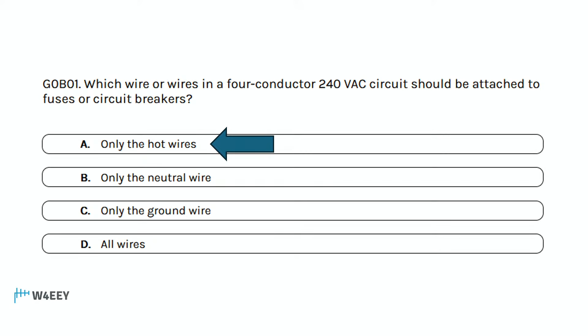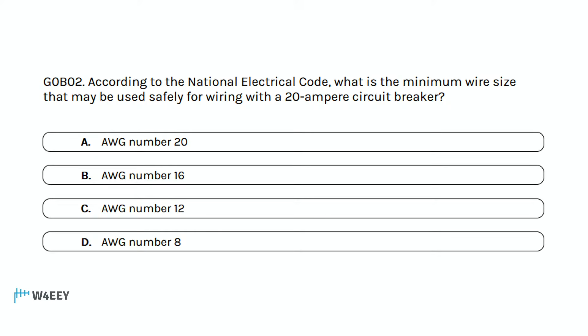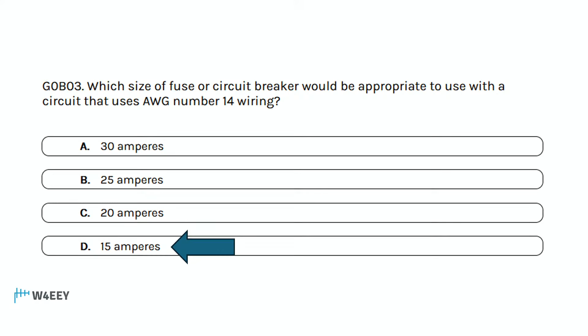Although 240 volts may have black and something else. According to the National Electrical Code, what is the minimum wire size that may be used safely for wiring with a 20-amp circuit breaker? Charlie. American wire gauge number 12. And which size of fuse or circuit breaker would be appropriate to use with a circuit that uses AWG number 14? Delta. Yeah, that's less. That's 15 amp ampacity.